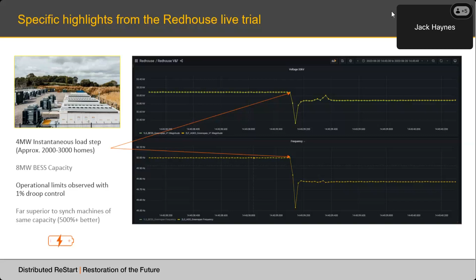Another highlight was the synchronization of the intact, so the power island that we generated, with the intact grid. What you can see happening here: the yellow line on the graph is the grid, and the light green line is the power island. So what you're seeing is the voltage, frequency, and angle difference between the grid and the power island that we've got. So the DRZC is monitoring what's happening on both sides.